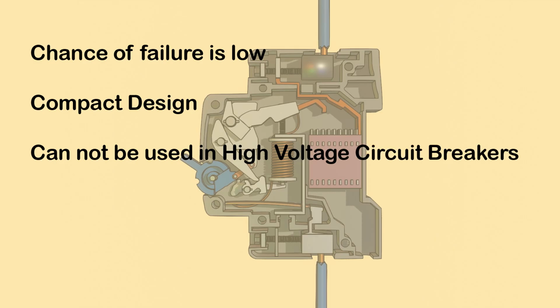However, this arrangement cannot be used in high voltage or high rated breakers, because in that case, the coil size would need to be very large, increasing the overall size of the breaker, which is not practical or economical. So series trip is suitable only for low voltage circuit breakers. Hope you got the idea of the trip mechanism. In the next video, we will discuss the difference between series trip and shunt trip.